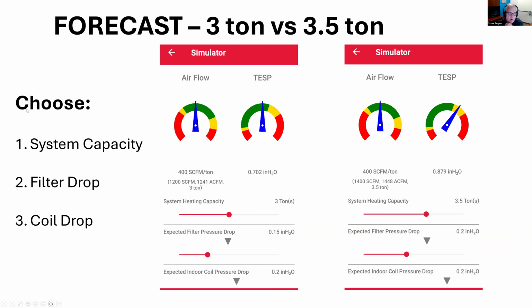So once I've given that information about what type of system it is, now I get to this simulator screen, and it's going to allow me to predict how that system's going to work once I choose three things. The top slider here is the system heating capacity, and then we get the filter pressure drop and the coil pressure drop. The filter pressure drop is usually available from the manufacturer, but you may need to adjust it for the airflow. So some experience with what you're measuring on existing systems with the filters that you're putting in new will be helpful there. The coil drop, that should be available in the manufacturer's literature.